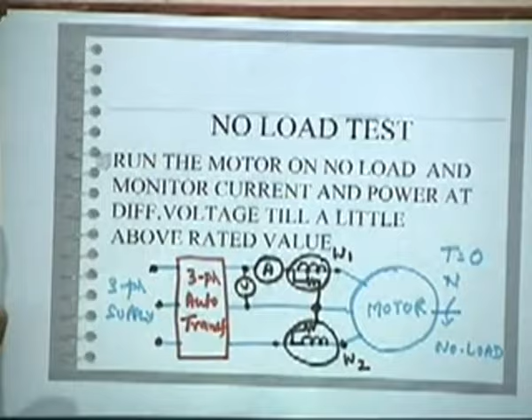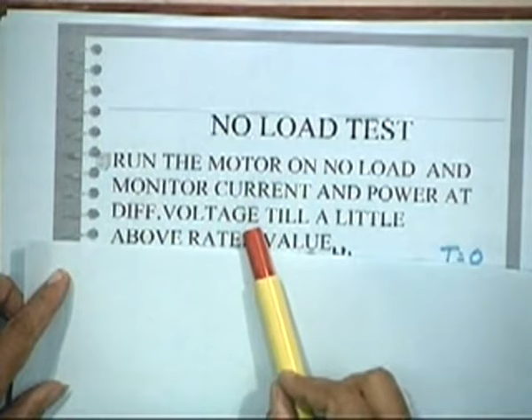So what we do is run the motor on no load, don't connect any load to the motor, then monitor the current and power at different voltages. So here you do it at different voltages, unlike in a blocked rotor test where you do it at different currents. Up to what voltage you can go? You can go till a little above the rated value. If it is rated at 415 volts, you can go to say 440, 450 like that, so a little more you can go.